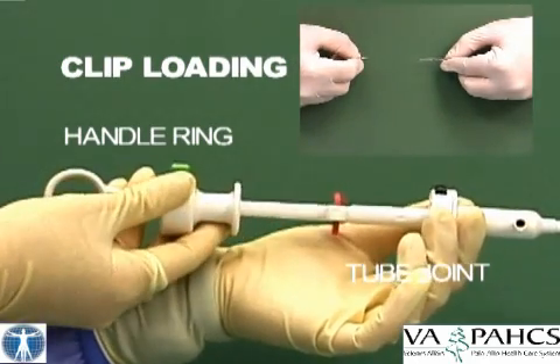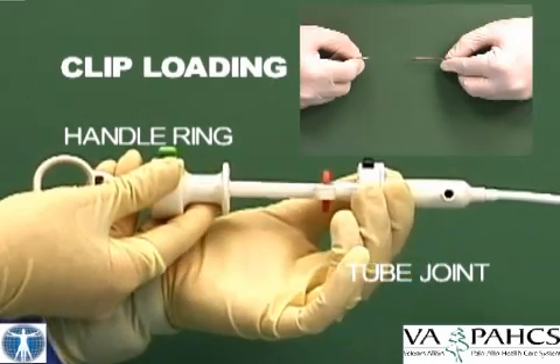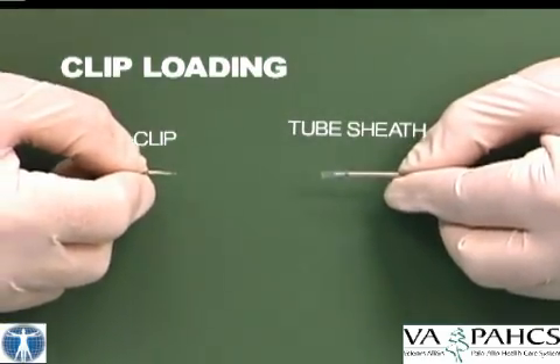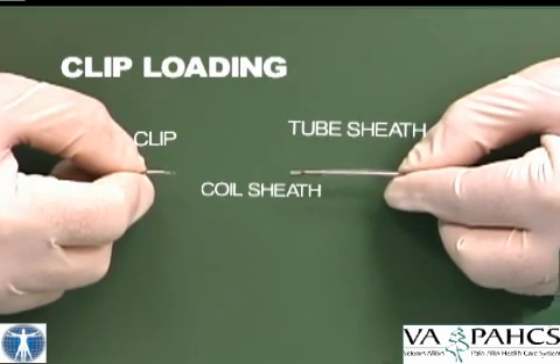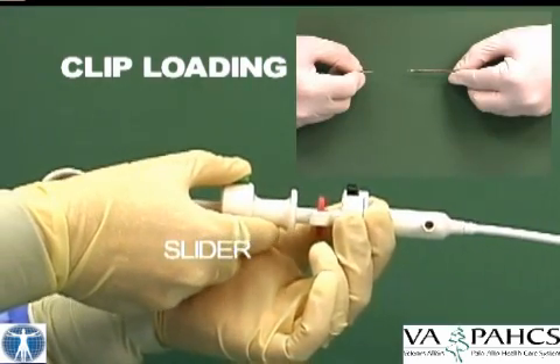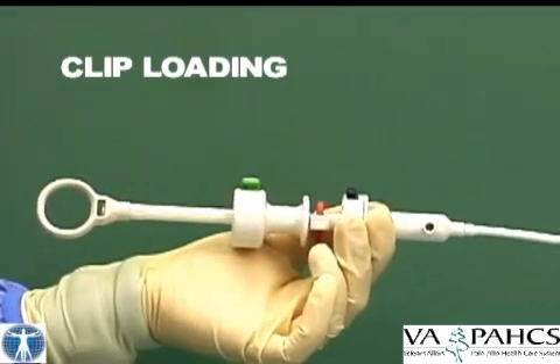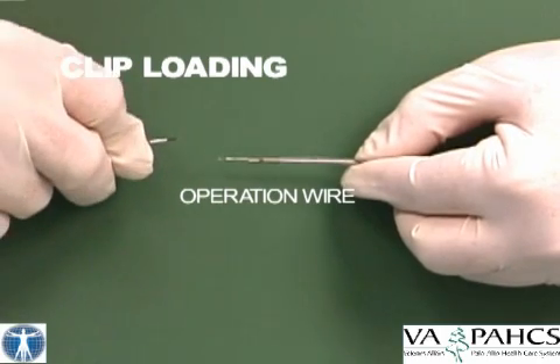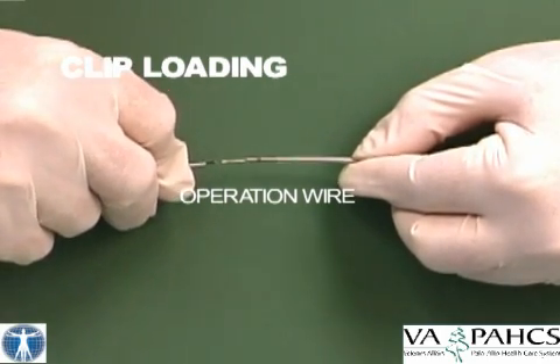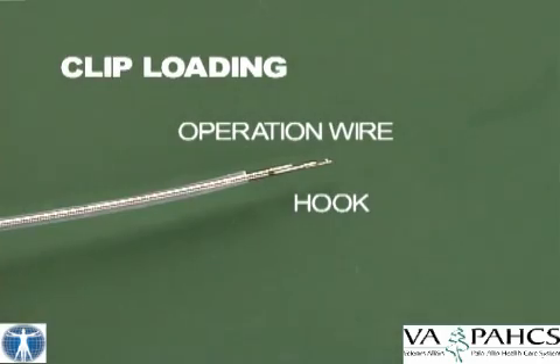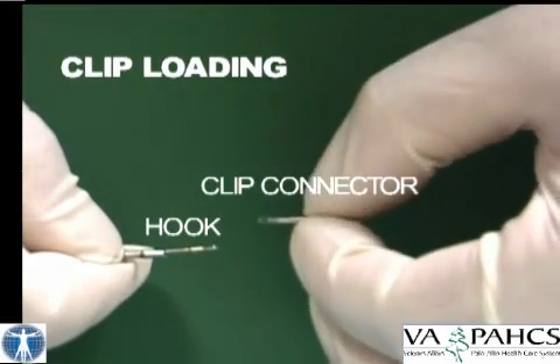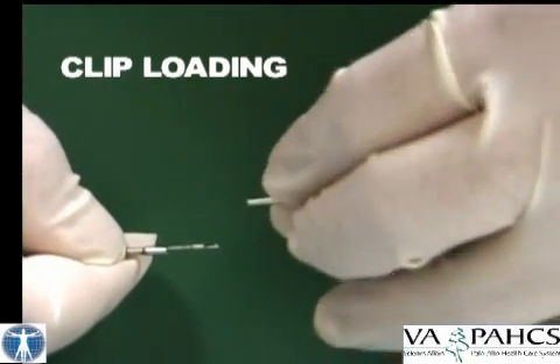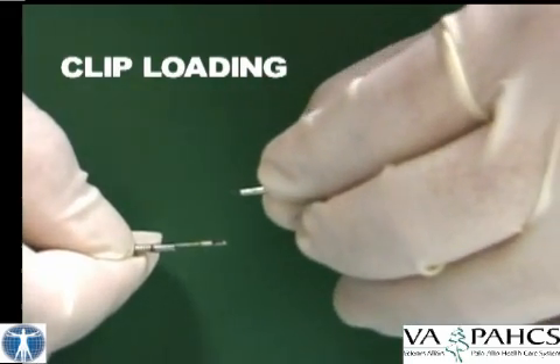To load the clip, start by sliding the tube joint toward the handle ring until a click is heard. This will expose the coil sheath from the tube sheath. Depress the green ratchet release button to push the slider away from the handle ring. This will expose the operation wire with the hook from the coil sheath. This is a close-up of the operation wire with the hook for mounting the clip connector. The clip is then mounted on the hook.